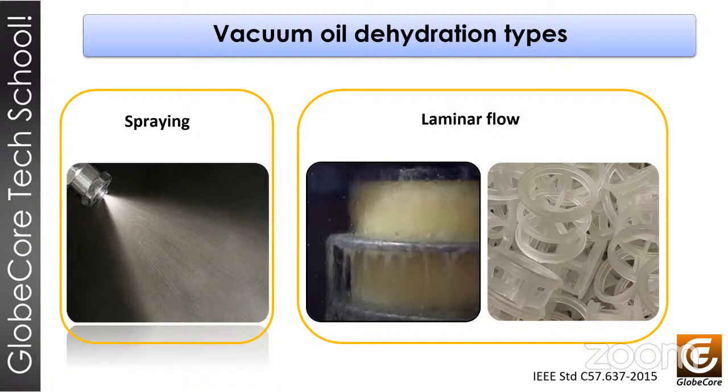Also, the Raschig rings and the Pall rings have similar cylindrical dimensions. The Pall rings have the advantage of two rows of punched holes with inwardly curved tabs, which greatly improves the performance of the nozzles in terms of throughput, efficiency, and pressure drop.